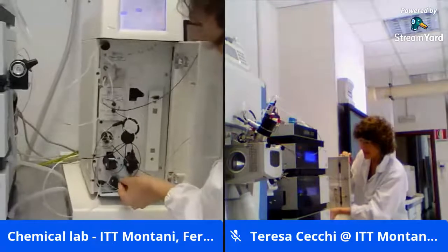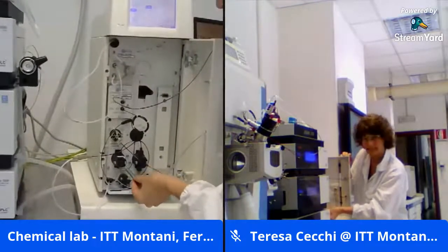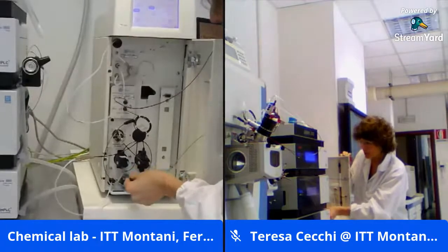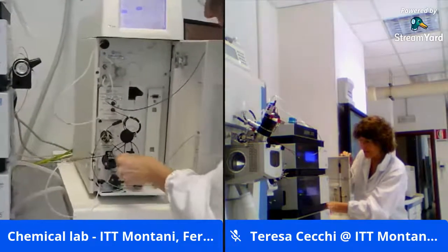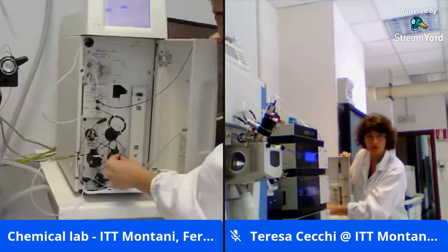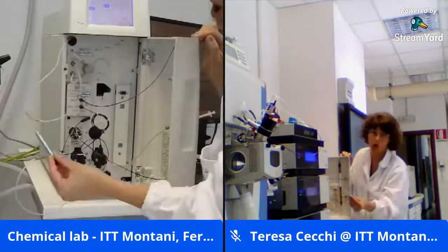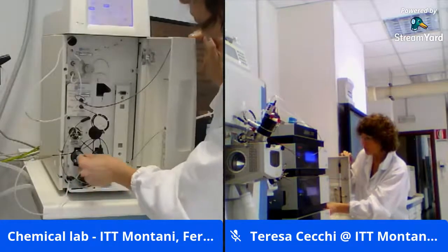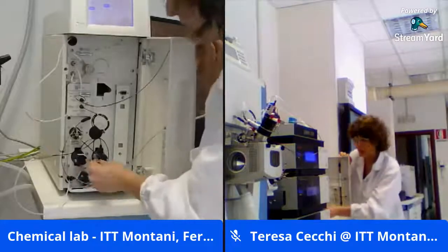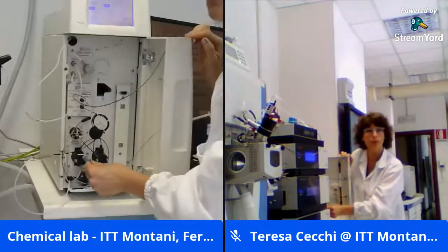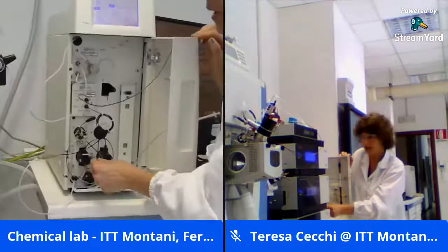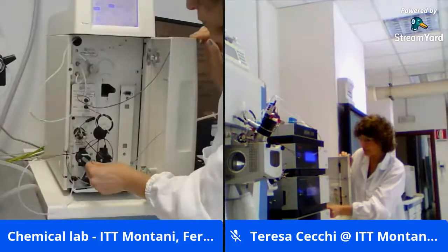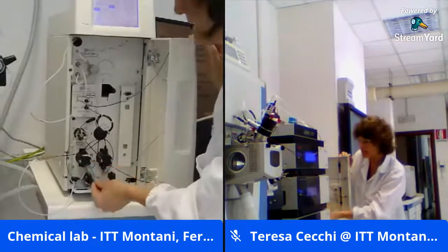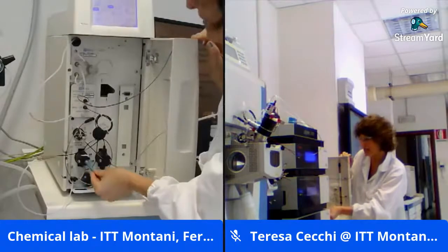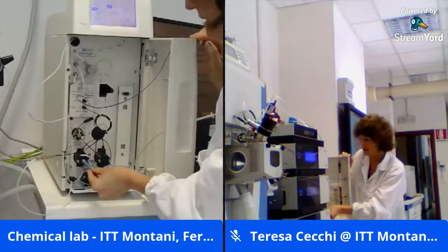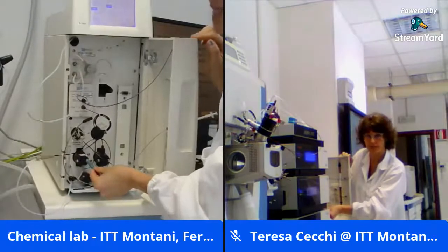This pump head has two outlets. The first one goes to the waste here, while the second one, with the narrow tubing, goes to the column sooner or later. And we have check valves inside the pumps to provide us with a one direction flow. And why do we find here also a valve? This is called the purge valve, and it enables the priming procedure.